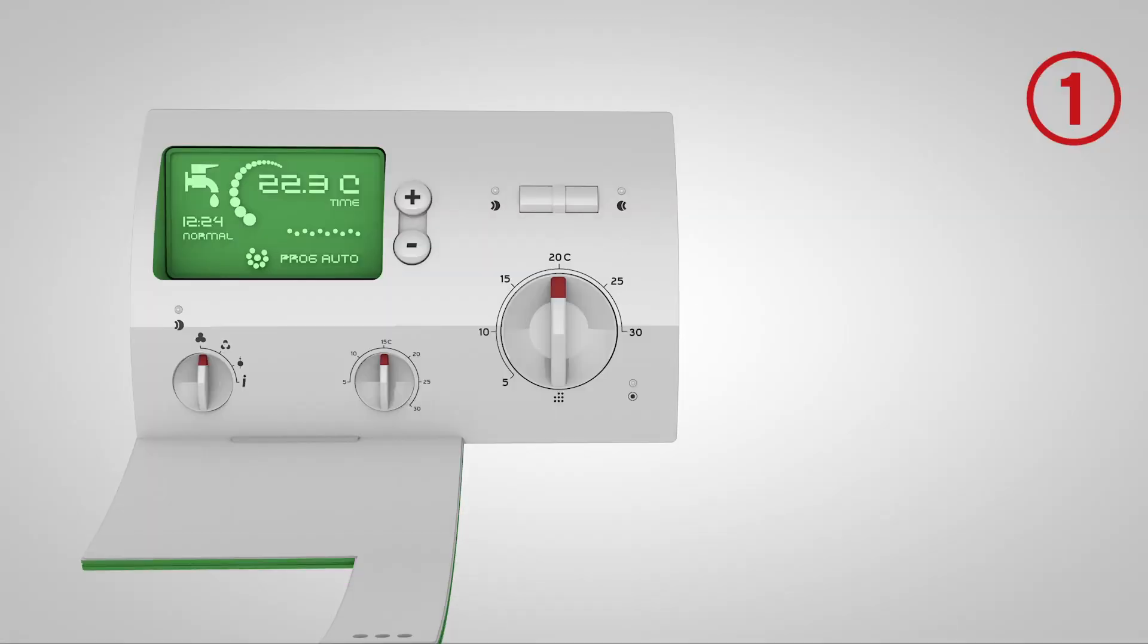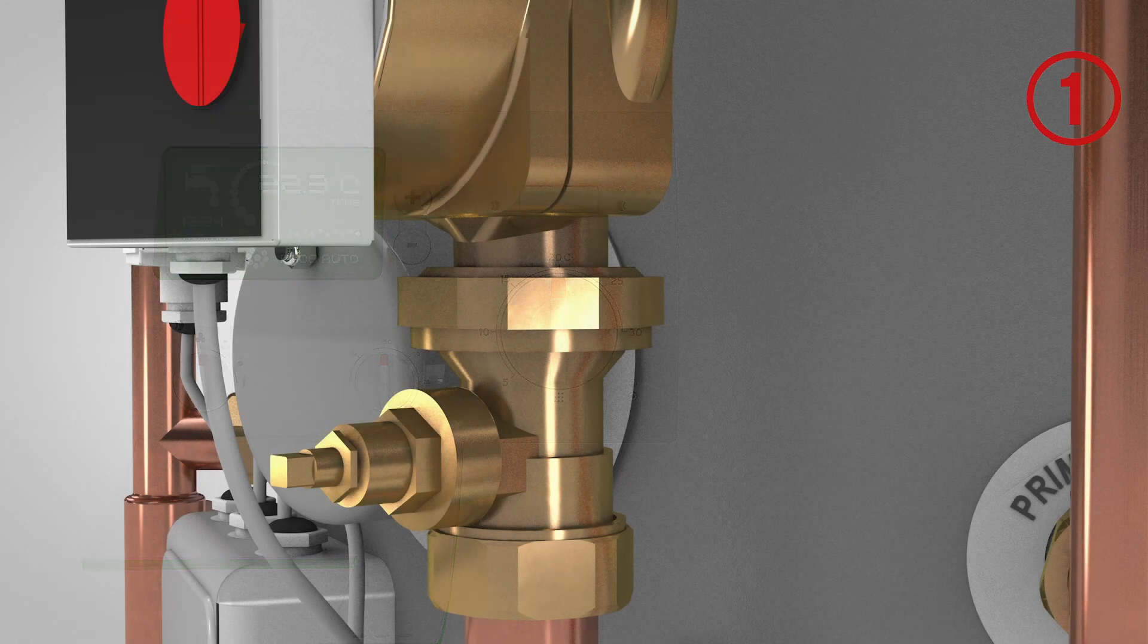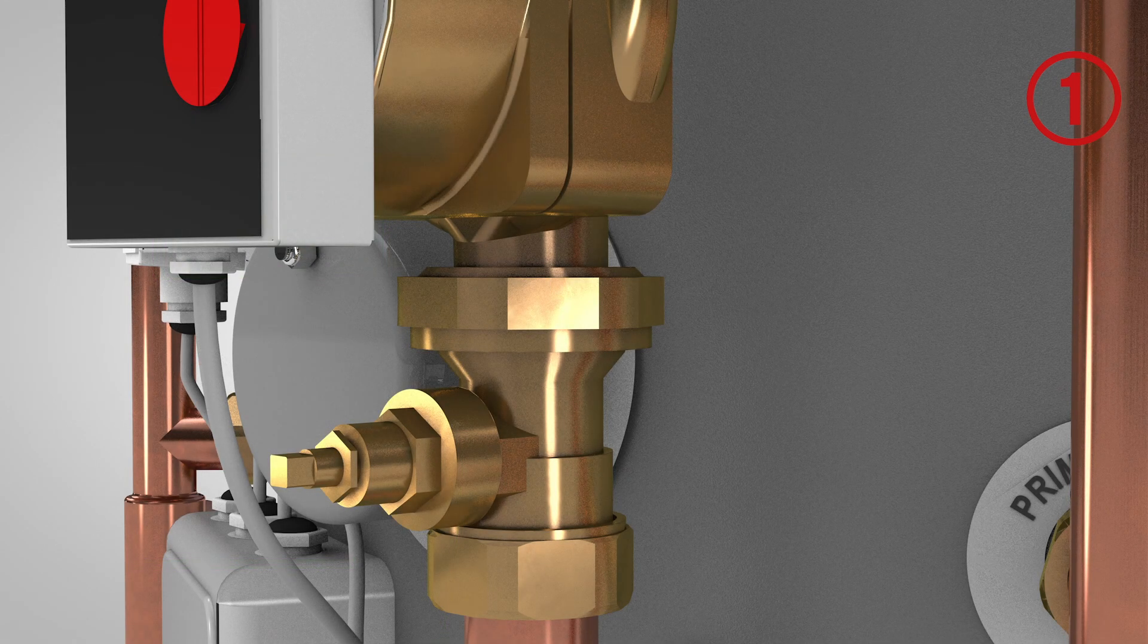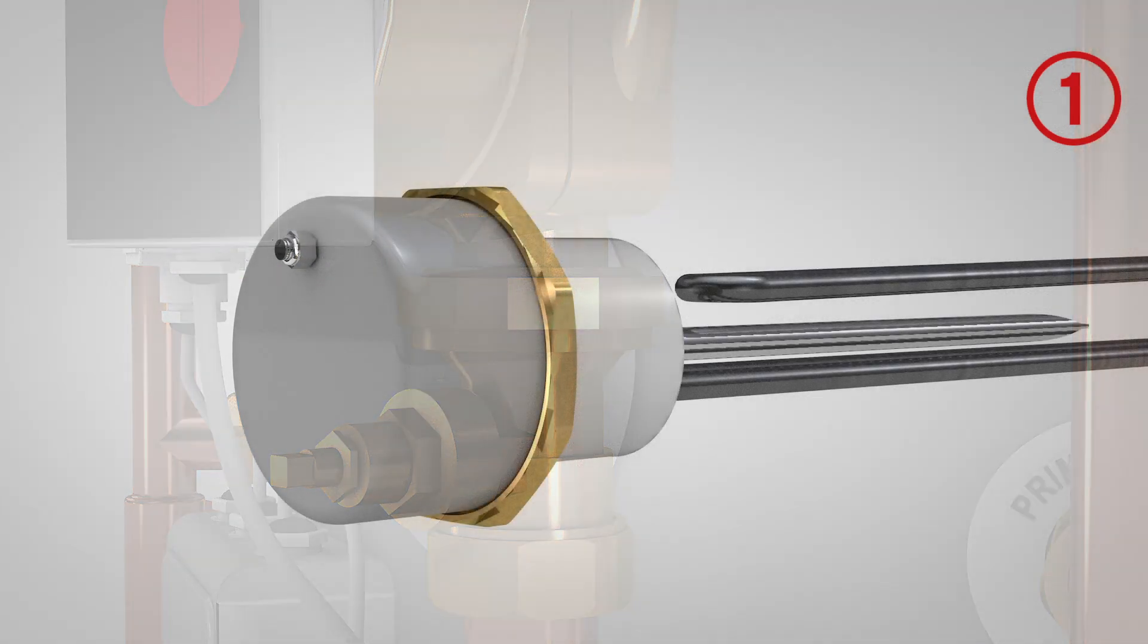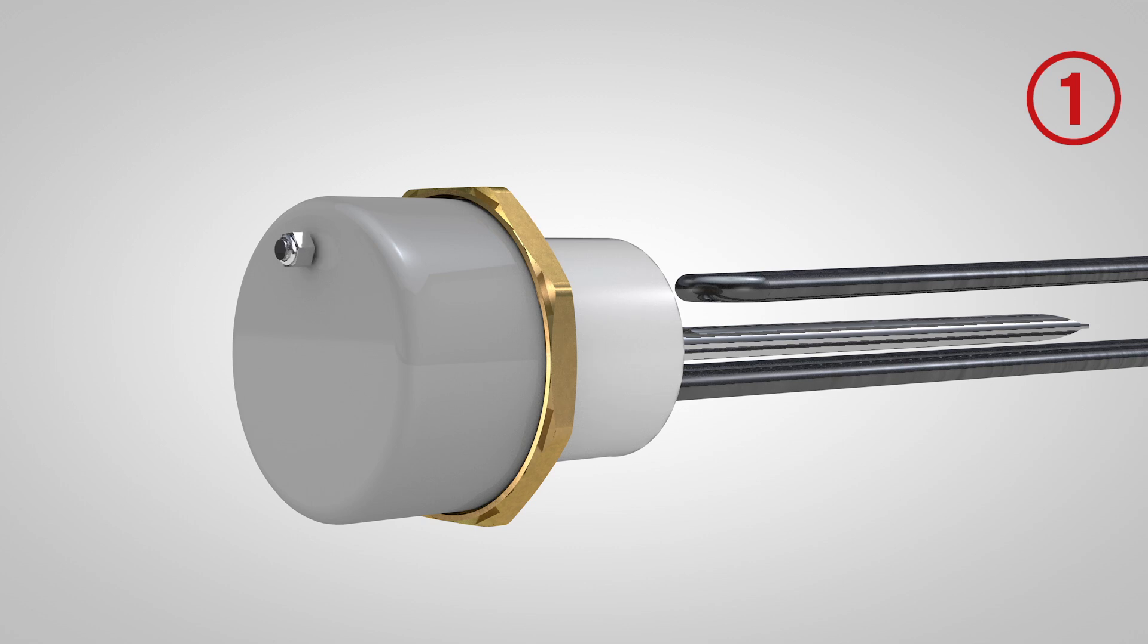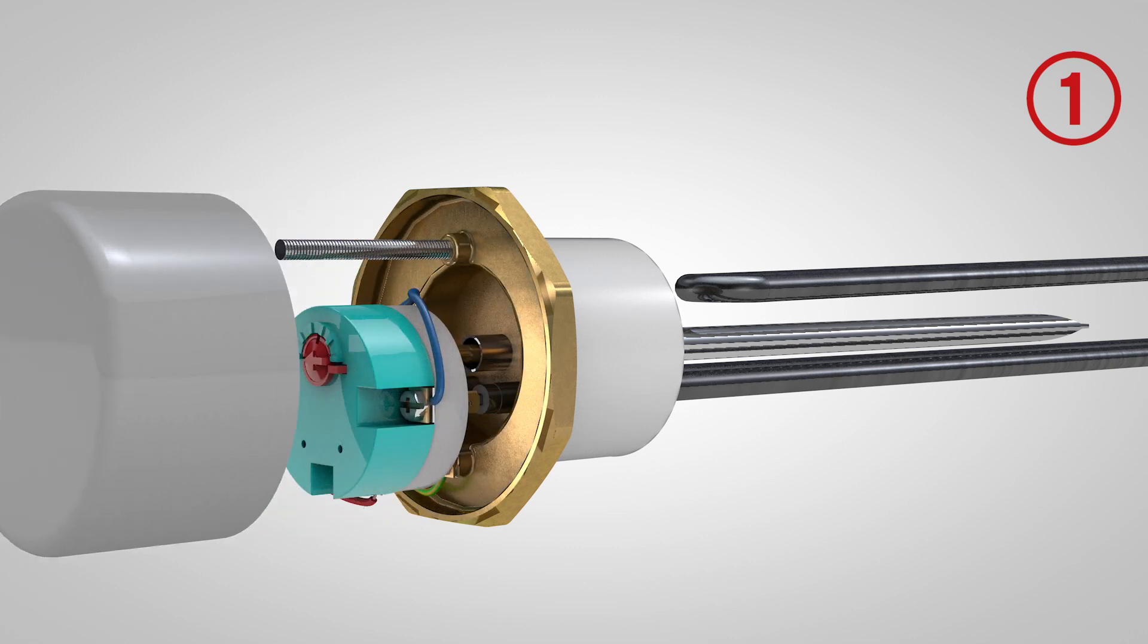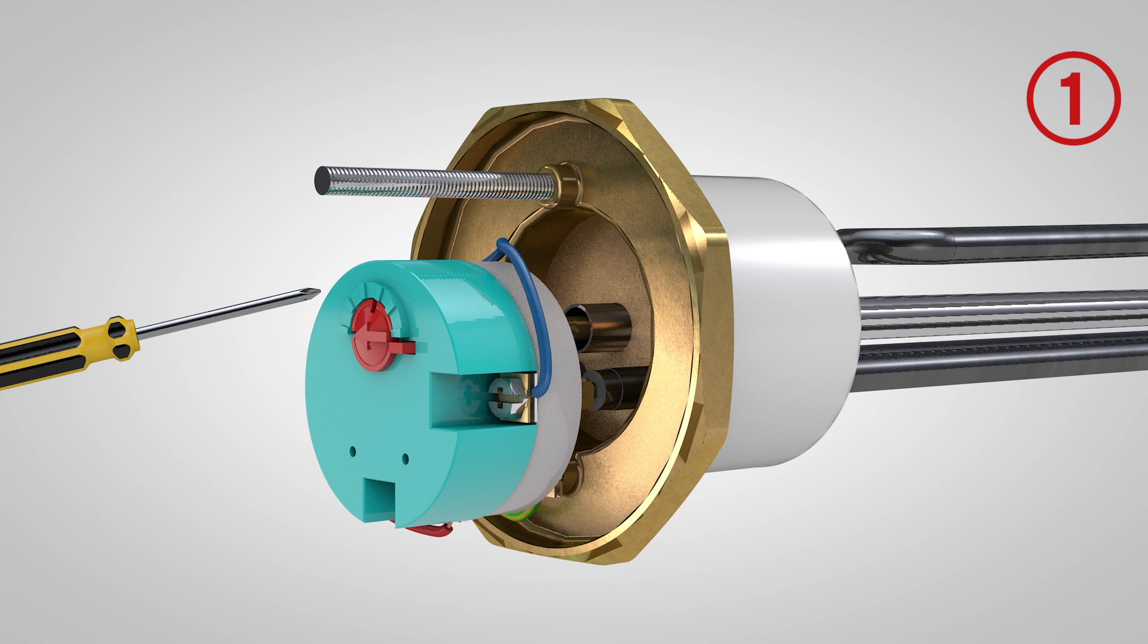The next most common problem to eliminate is to check if the high temperature cutout has popped. To check the thermostat on the immersion heater, isolate it from the power supply and remove the cover. Locate the reset switch on the thermostat and press it down.